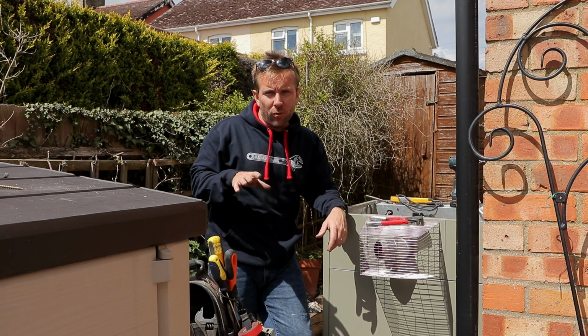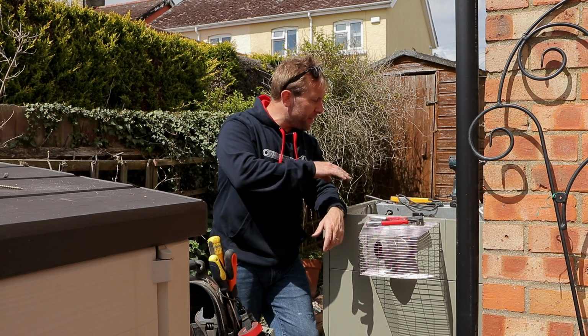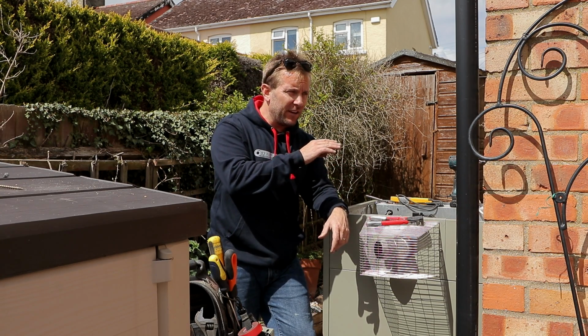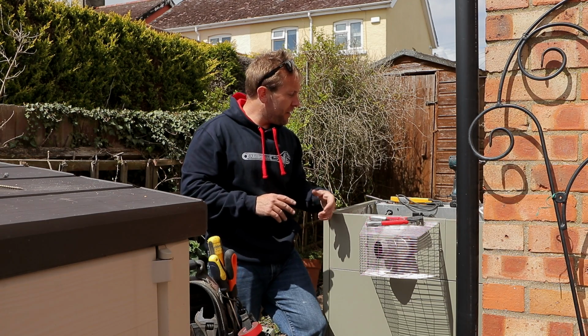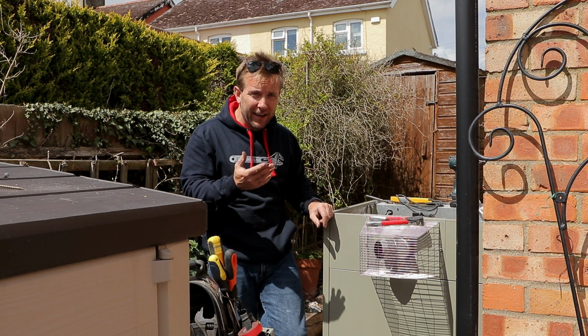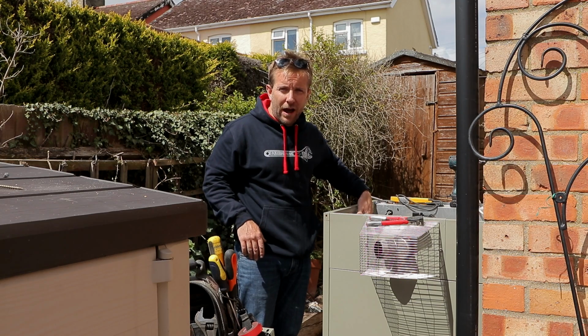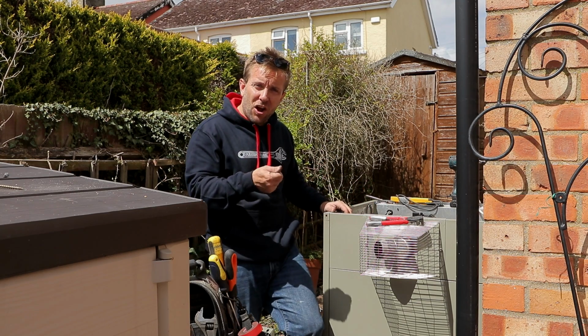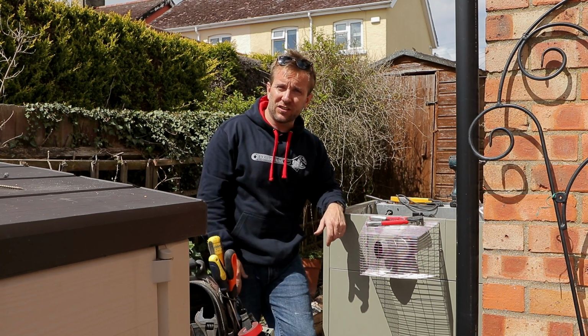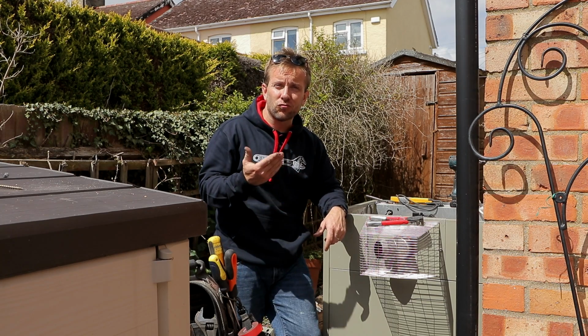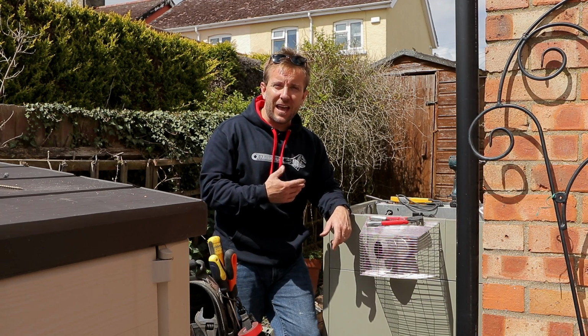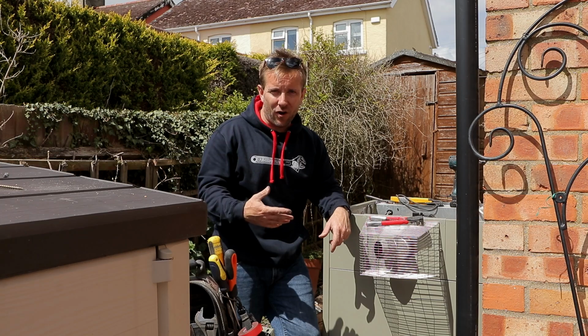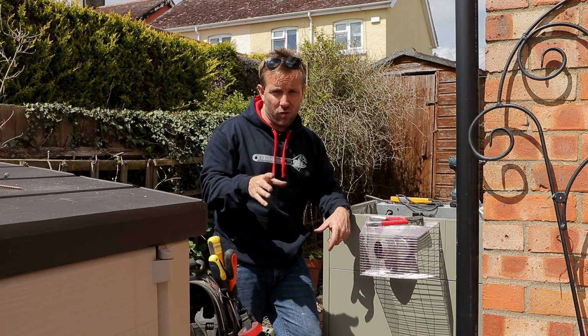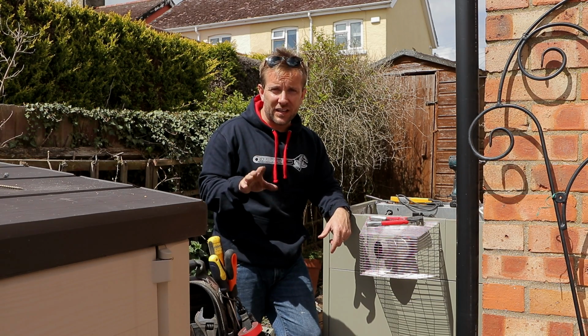Right, I've done one or two more tests as well. I shut the valves going off out onto the heating system, then watched the pressure go up, turned our cold water mains valve off, and went inside and opened up a hot tap. Guess what I saw? The pressure on the boiler side dropped. That means we're getting boiler side water coming out the hot taps, which is something we don't want at all. So now I'm happy to change over this heat exchanger.